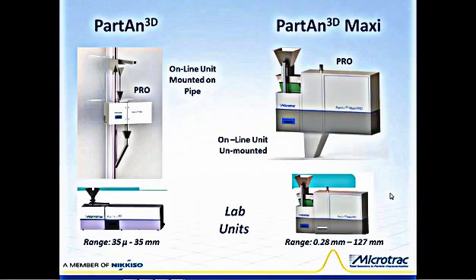The upper left photo shows the PartAn 3D Pro, Pro for online process version, and it's shown here mounted on a pipe, sampling and measuring the sample stream and returning it to the process. At lower left is the lab version. The upper right photo shows the PartAn 3D Maxi Pro, unmounted on a process stream, and below it the lab version.